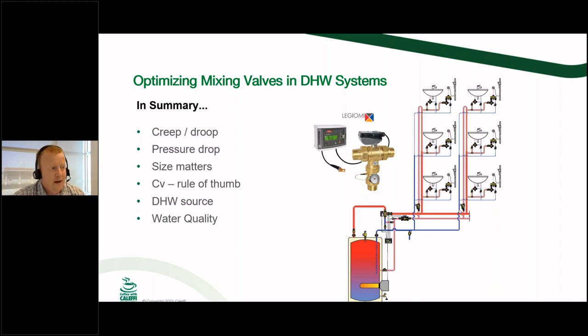Like I said before too, I've had plenty of customers where they do two of them in parallel, two mixing valves in parallel. And it's not because they need the redundancy or the higher flow capabilities of two mixing valves. It's because they wanted to do a lead lag, so that way they can do maintenance on one while keeping the building operational and not having any interruptions in service.